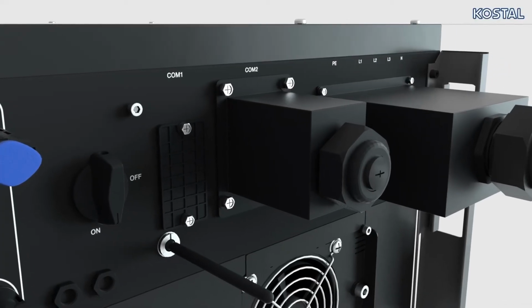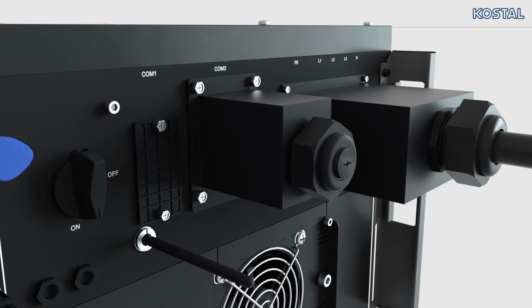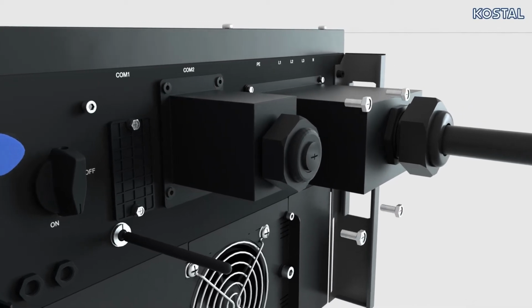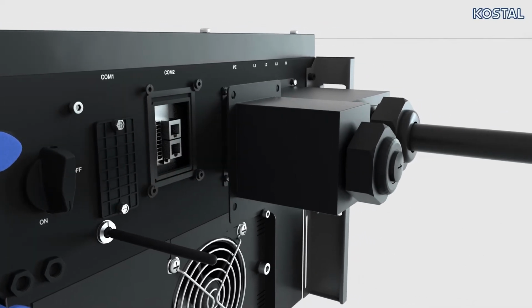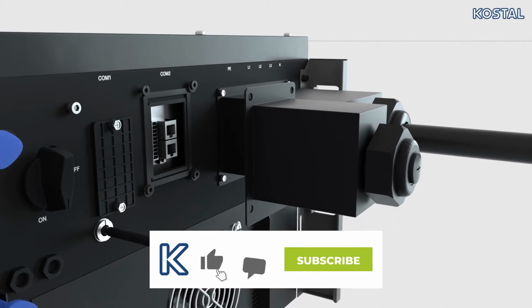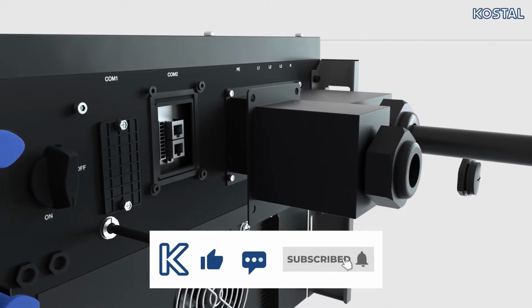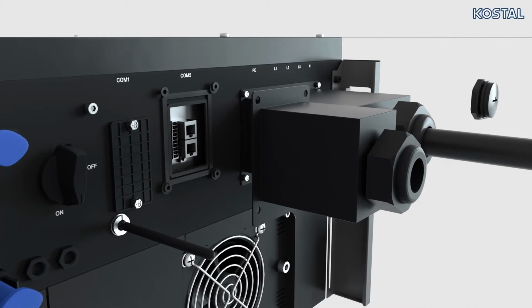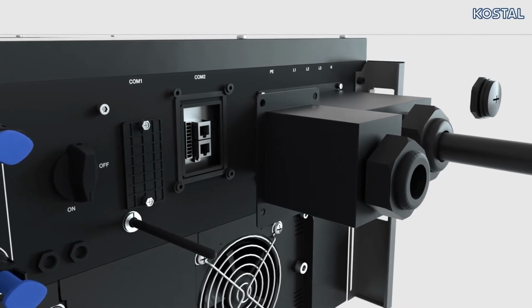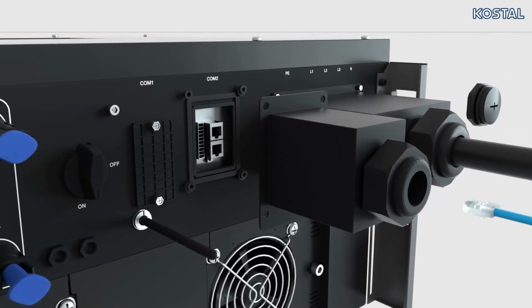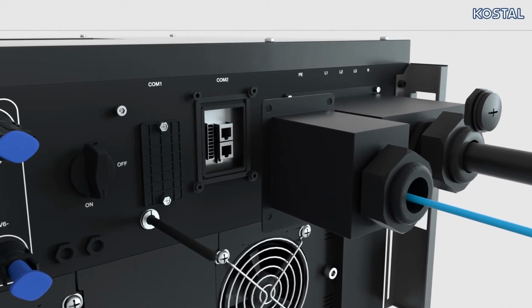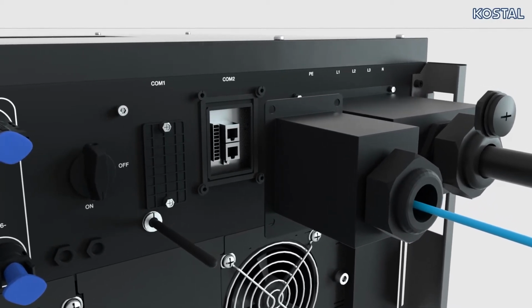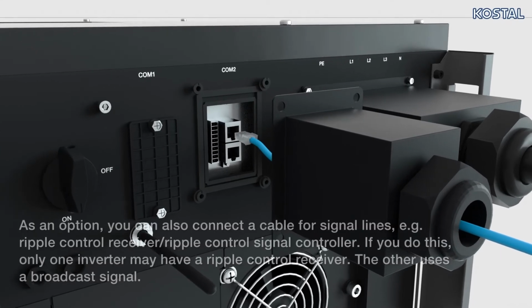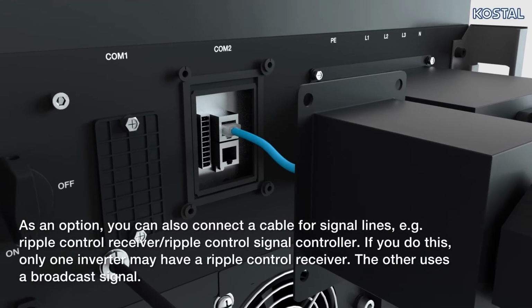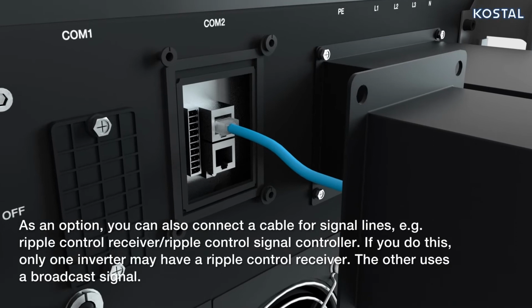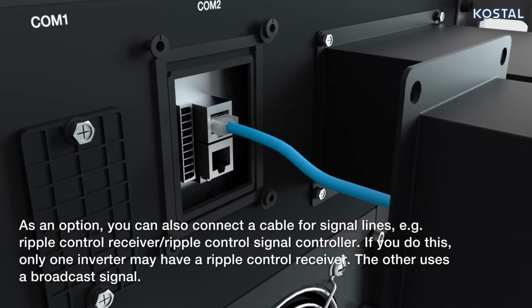Establish the internet connection with your inverter at the COM2 connector panel. Start by releasing the screws from the cover and removing the cover. Remove the plug seal and replace it with the appropriate plug with multiple ducts, which is supplied. Guide the Ethernet cable through the COM2 cover and connect it to one of the 2 LAN RJ45 sockets. Seal the LAN cable with a sealing ring and union nut.